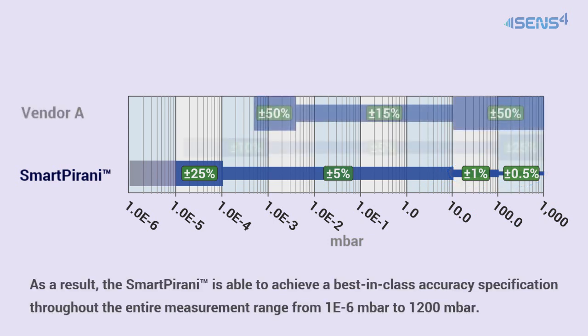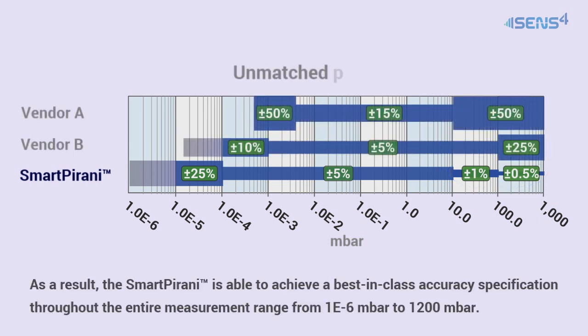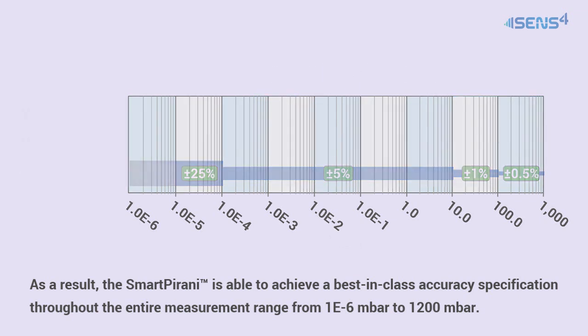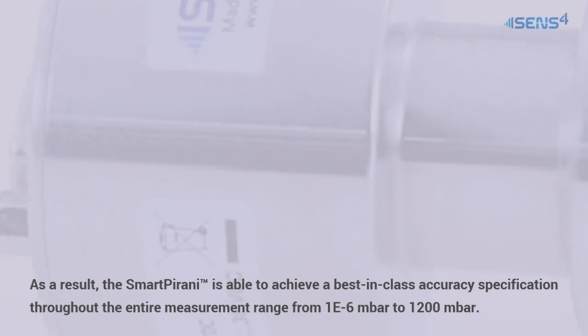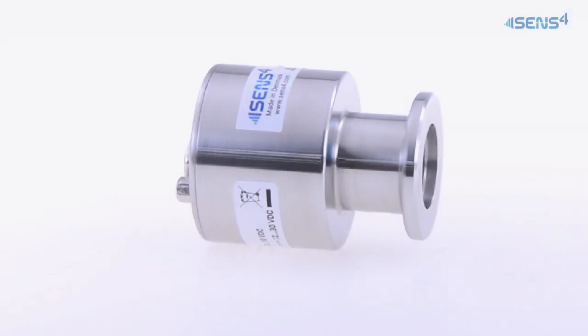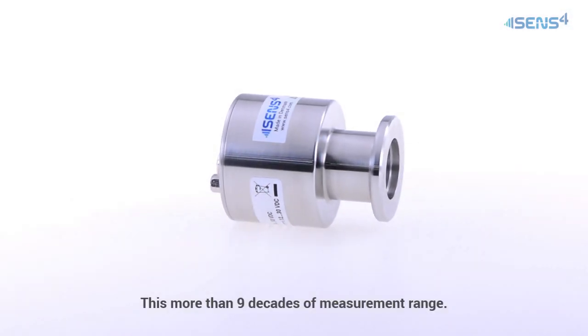As a result, the SmartPirani is able to achieve a best-in-class accuracy specification throughout the entire measurement range from 1E-6 millibar to 1200 millibar. This is more than 9 decades of measurement range.